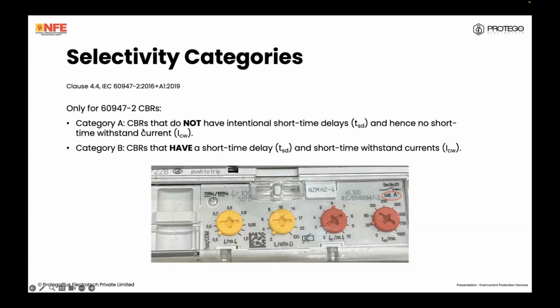There are circuit breakers that have a time delay, and there are circuit breakers that do not have a time delay. These are defined. So you see here, this breaker has a time delay. It's written CAT A, which is category A. Sorry, just one moment. I think this is the other way around. So, circuit break. No, yeah, sorry, my bad. Circuit breakers that do not have an intentional short time delay, and therefore they will have no rated withstand current. Circuit breakers at category B, they have a short time delay and they have a rated short time withstand current, which means that for a given short circuit, it will wait a certain amount of time, but the internal components are able to withstand that current and the electrical energy, and what is the rated short withstand current.